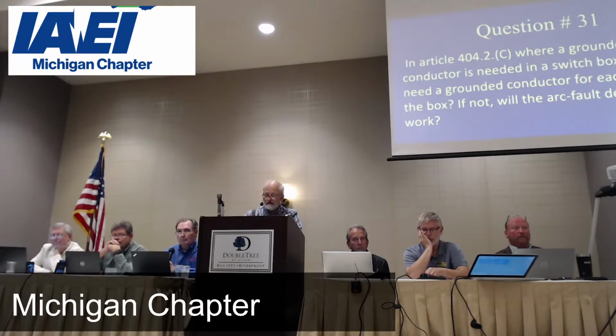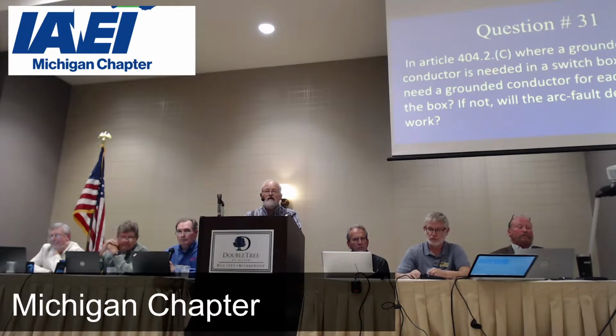Well, that one also requires a neutral. Fortunately, whoever wired it did it in a way that there was a neutral at both locations, and it worked. But without that neutral, it wouldn't work. So it's something for people to keep an eye out for.